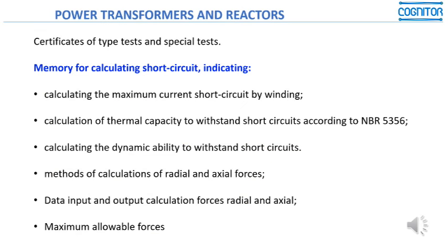Then, for power transformers and reactors, many of the specifications are similar to the ones that we presented before, but there is something interesting for power transformers. As this equipment is most of the time very heavy and difficult, and in many cases can be very big and difficult to bring to a testing laboratory to do tests, to do a short-circuit test, for example, the IEC standard permits that tests are replaced by a memory of calculation of short circuits.